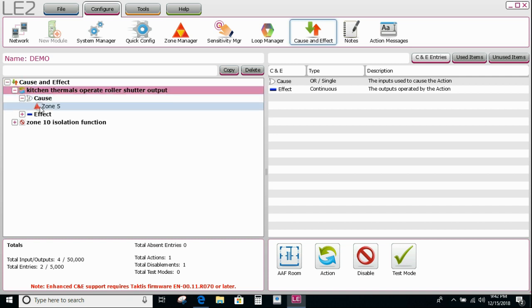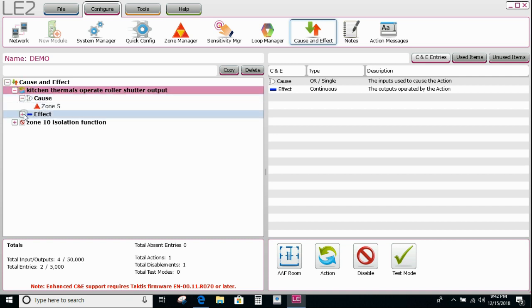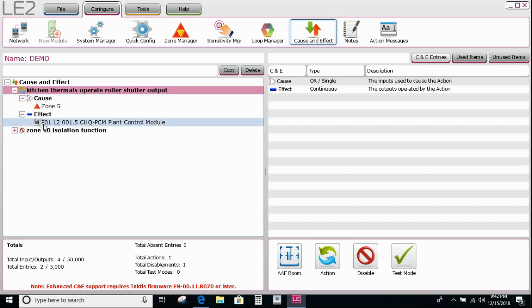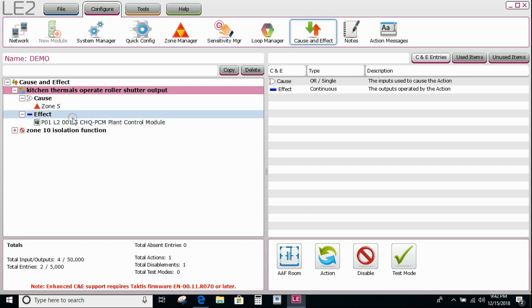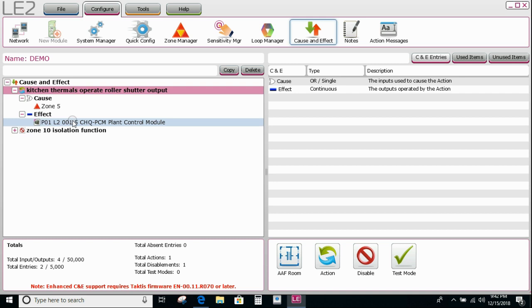We open it up and it's saying any detector in zone 5 will operate this relay. And the only thing that will operate this is this cause and effect, because we unchecked the default ring mode for that output. That's how we can set up an action type cause and effect.